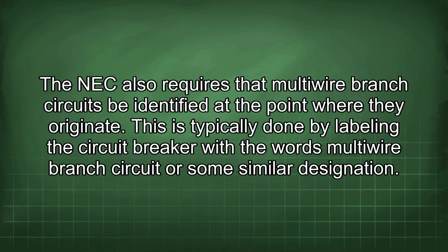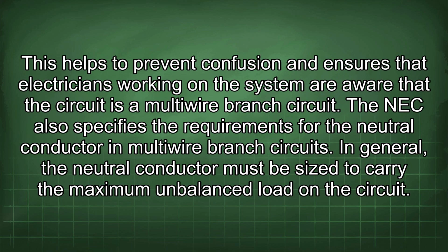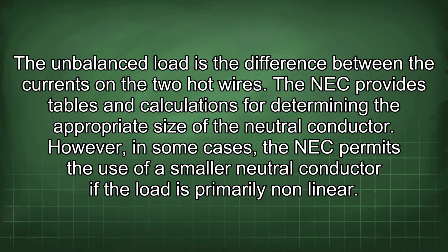This requirement is intended to prevent the neutral wire from becoming overloaded if one of the hot wires trips independently. The NEC also requires that multi-wire branch circuits be identified at the point where they originate. This is typically done by labeling the circuit breaker with the words multi-wire branch circuit or some similar designation. This helps to prevent confusion and ensures that electricians working on the system are aware that the circuit is a multi-wire branch circuit. The NEC also specifies the requirements for the neutral conductor in multi-wire branch circuits. In general, the neutral conductor must be sized to carry the maximum unbalanced load on the circuit. The unbalanced load is the difference between the currents on the two hot wires. The NEC provides tables and calculations for determining the appropriate size of the neutral conductor.